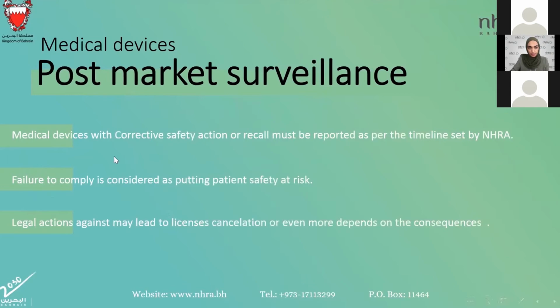Post-market surveillance: medical devices with corrective safety action or recall must be reported as per the timeline set by NHRA. Failure to comply is considered as putting patient safety at risk. A legal action will be taken, and it might lead to a license cancellation or even more, depending on the consequences that this delay caused. If it caused death, God forbid, it will cause more than this legal action.